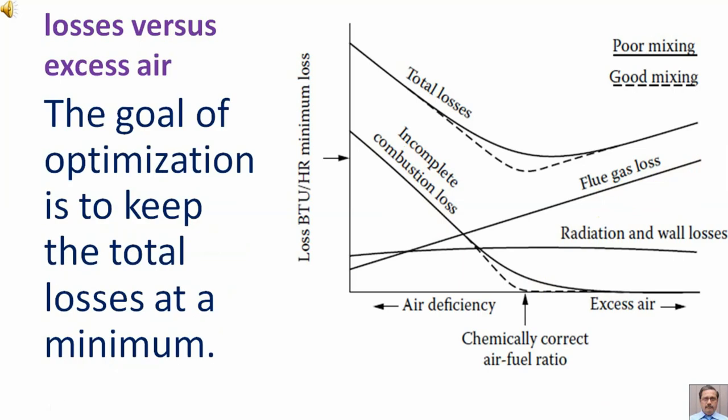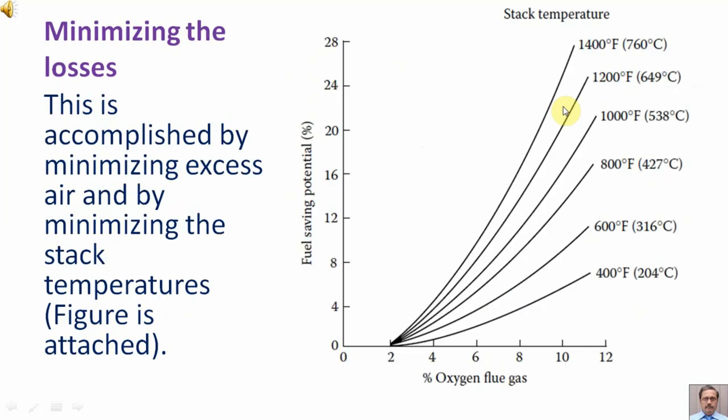The goal of optimization is to keep the total losses at a minimum. This is accomplished by minimizing excess air and by minimizing the stack temperatures. Figure is attached.